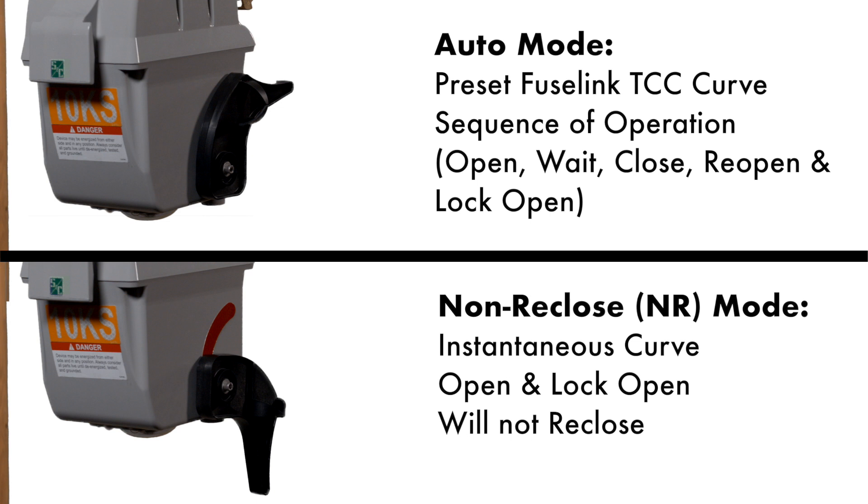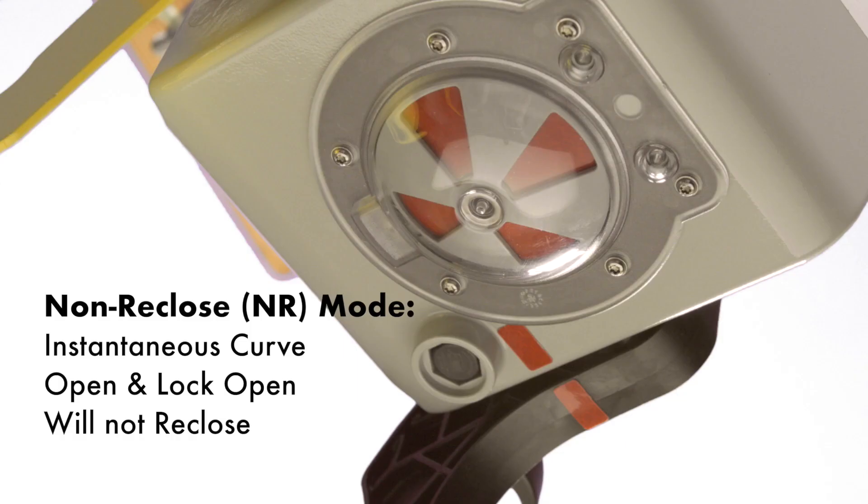In the NR mode, the VacuFuse interrupter will operate using the instantaneous curve. The interrupter will open and lock open and not attempt to re-close if a fault occurs while NR mode is selected. The VacuFuse self-resetting interrupter is in the NR mode when the red line on the lever matches up with the red line on the base of the interrupter's housing.